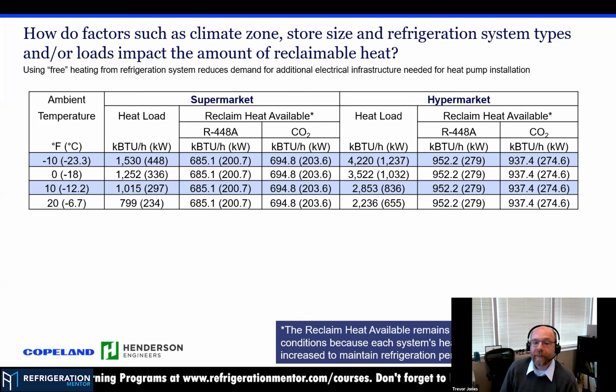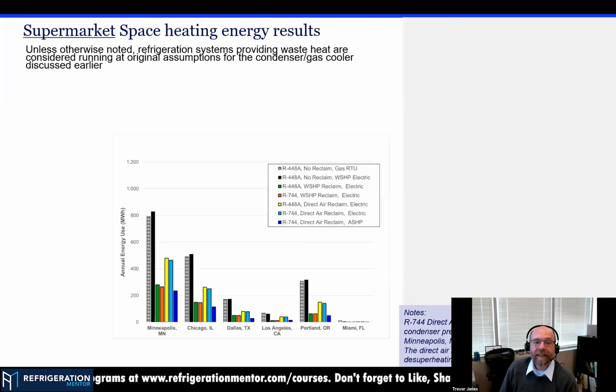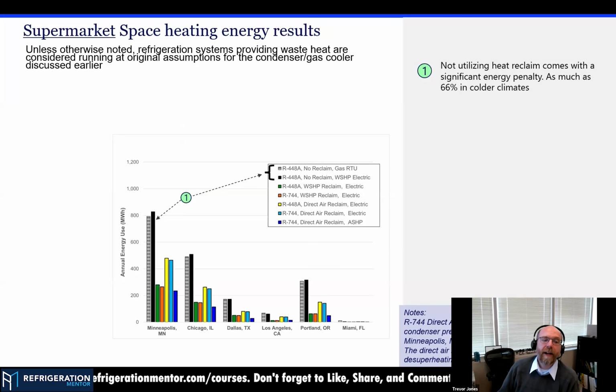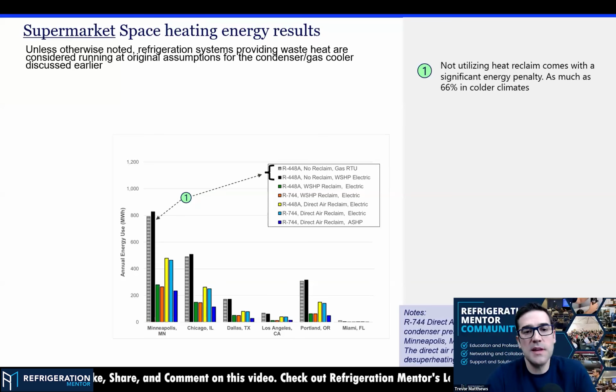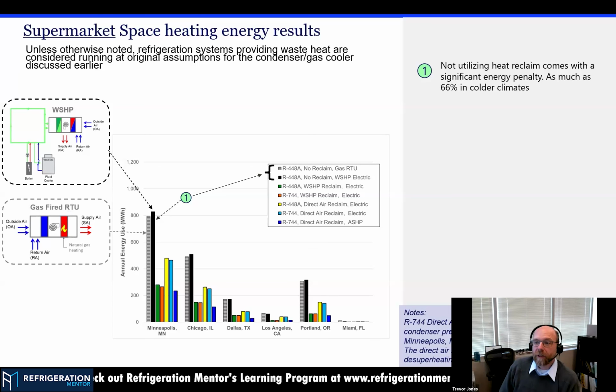Okay, fantastic. And now looking at some of the total energy use. Right off, you can see there's a big penalty in not using any of the reclaimed heat, and that's for each location. Well, it makes sense. We're just throwing that heat away, right? We're creating heat, and then we're just throwing it out the gas cooler or the condenser, depending on the application. So those are the two systems we've looked at.